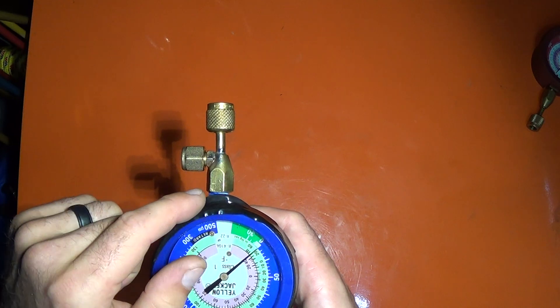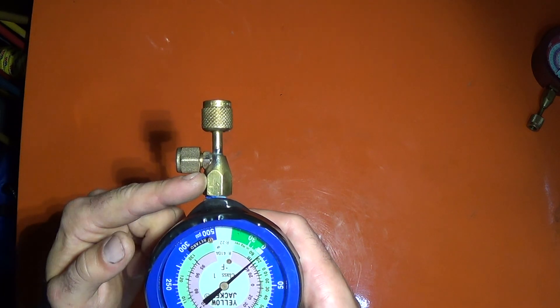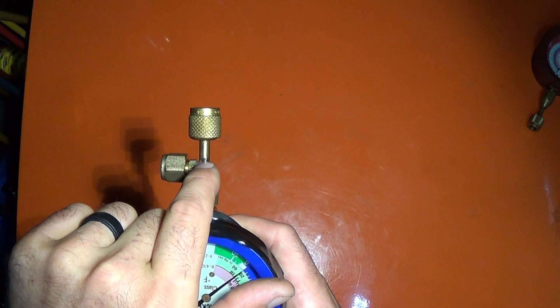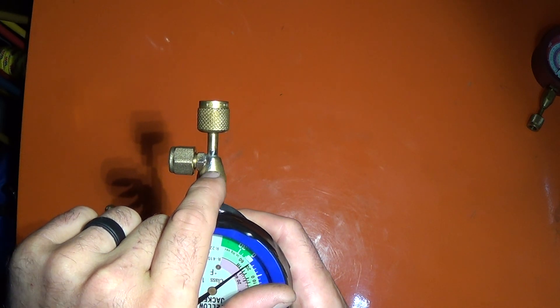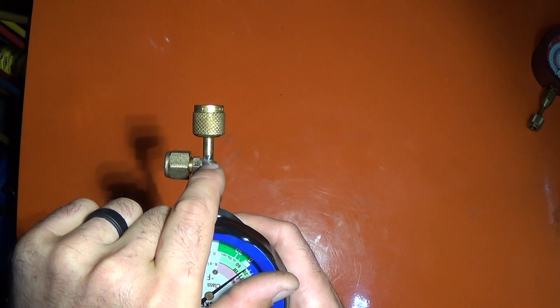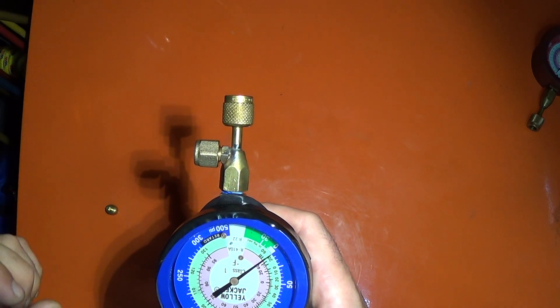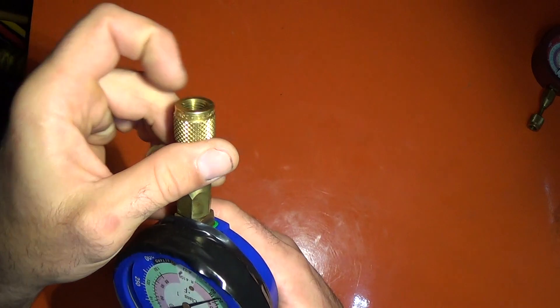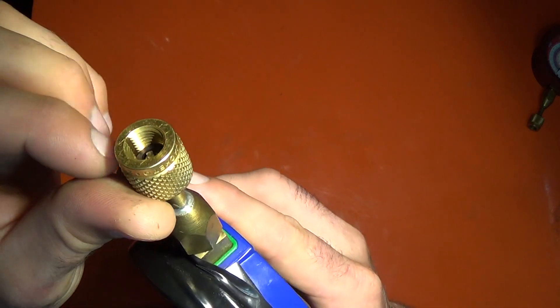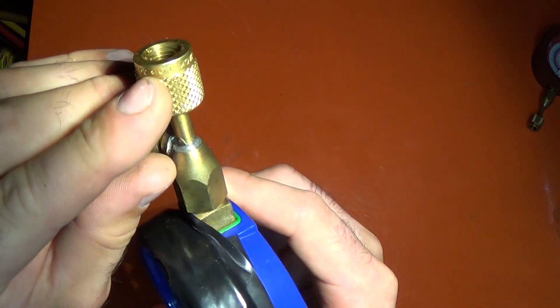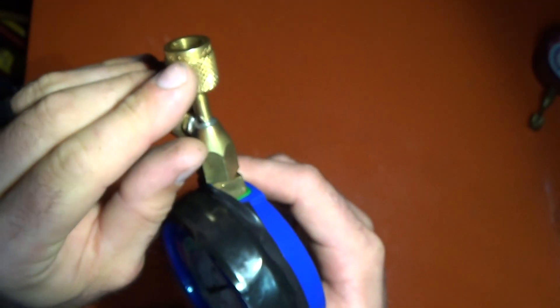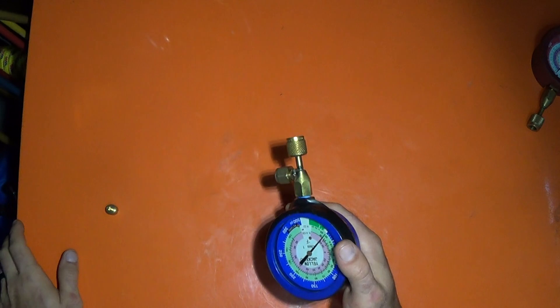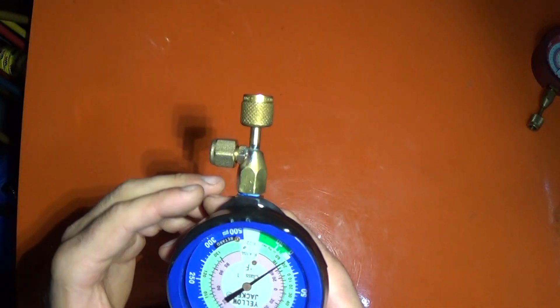Then you're going to melt a little braise on the top and use your heat to flow it down and you're going to hit this. I didn't hit this initially. And I think what Yellow Jacket did was actually solder this in and not braise. In the heat from braising, it just created a bunch of little pinholes as that solder vaporized. So anyways, you want to hit this and hit that. And then if you have a problem getting this to seal, I think what I did, you can see how there's kind of a fillet around there. I actually just went and went over it with a Stay-Brite 8 and just laid a fillet over that to seal it. But I did that several years ago and it's been absolutely great ever since.